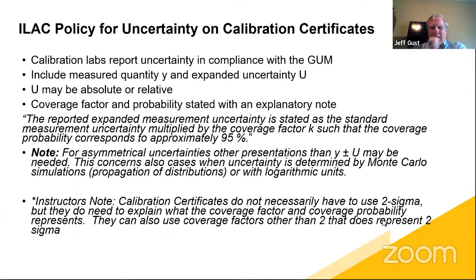And also, labs can use coverage factors other than 2 if they represent 2 sigma. So again, maybe you're using a combined effective degrees of freedom with a Welch-Satterthwaite equation, and you come up with 5 degrees of freedom out of that process to get to 2 sigma level of confidence, so your coverage factor needs to be 2.65. That's just an example off the top of my head. So your k value, your coverage factor, might be different than 2, but it does represent 2 sigma at the end of the day. More about that in further uncertainty training.